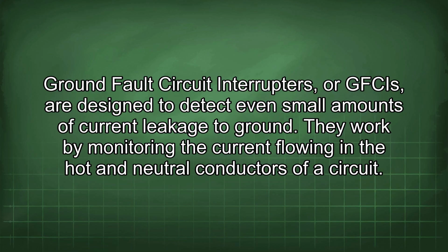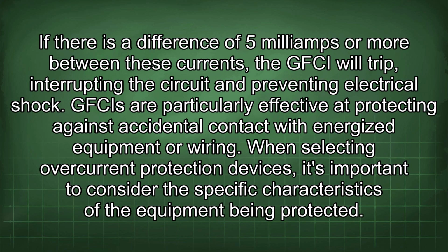They work by monitoring the current flowing in the hot and neutral conductors of a circuit. If there is a difference of 5 milliamps or more between these currents, the GFCI will trip, interrupting the circuit and preventing electrical shock. GFCIs are particularly effective at protecting against accidental contact with energized equipment or wiring.